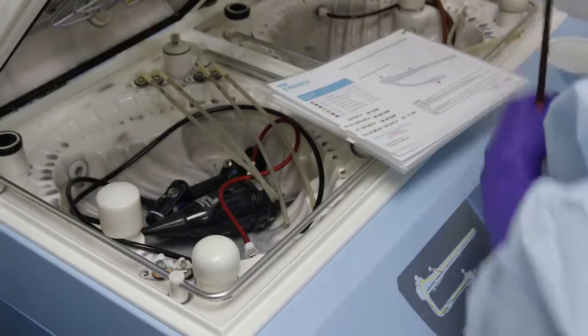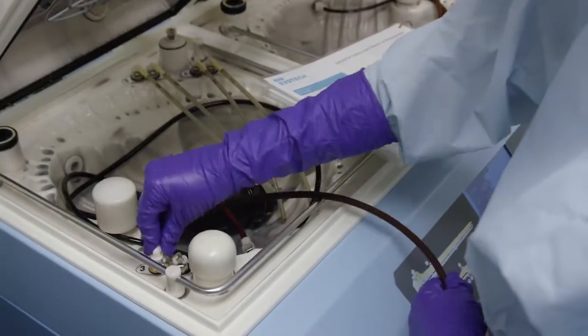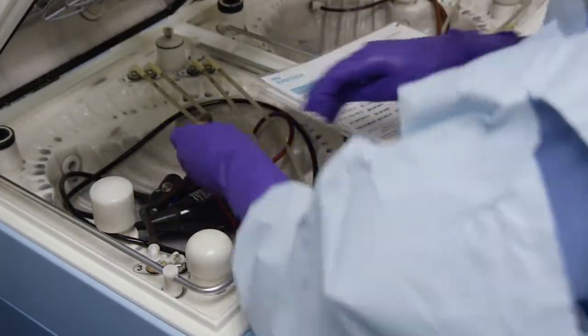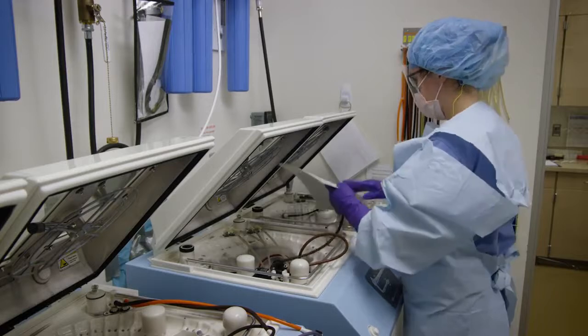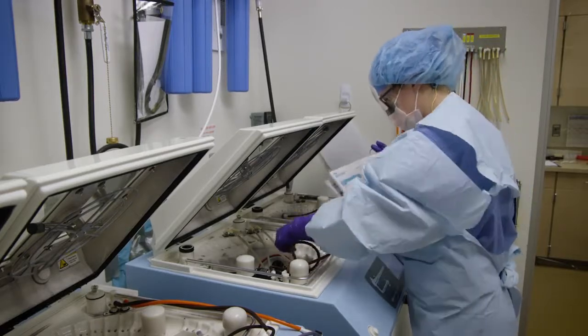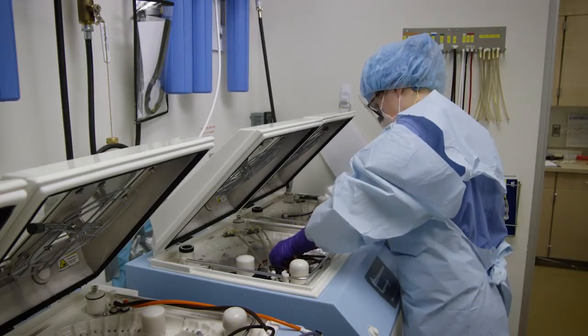In my view, it's much safer to use an automated reprocessing system that can take those steps away from the staff, make sure that they're done properly for the right time at the right temperature without employee exposure to those chemicals. AERs are automated with regard to immersion, filling channels with solution, timing the exposure period, and rinsing with water to remove the solution residue.